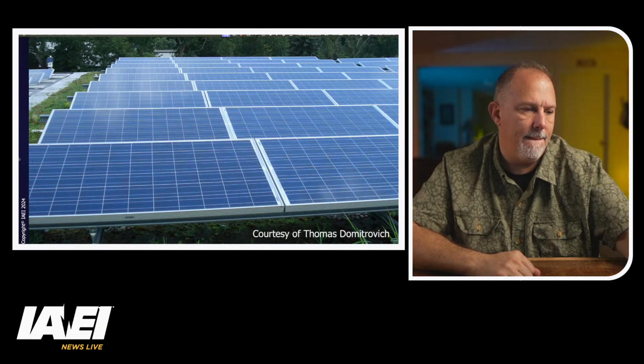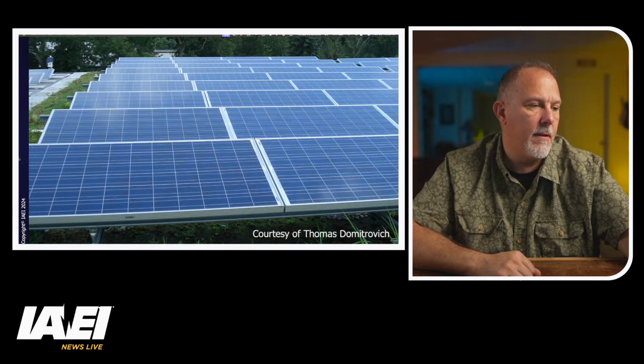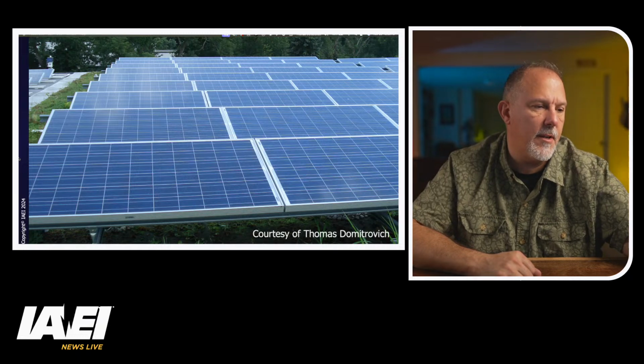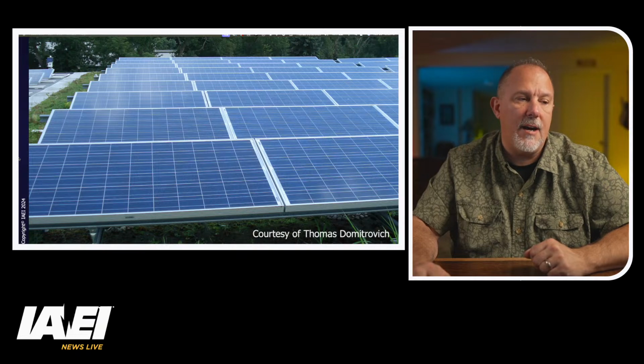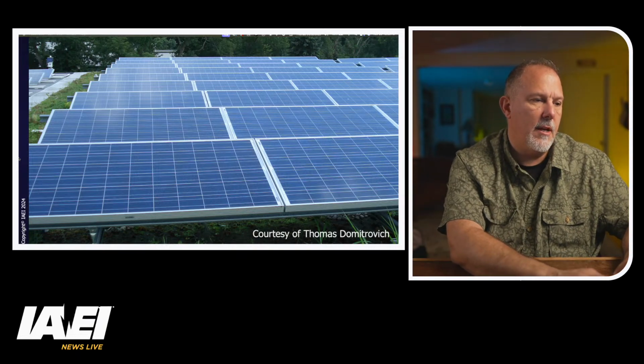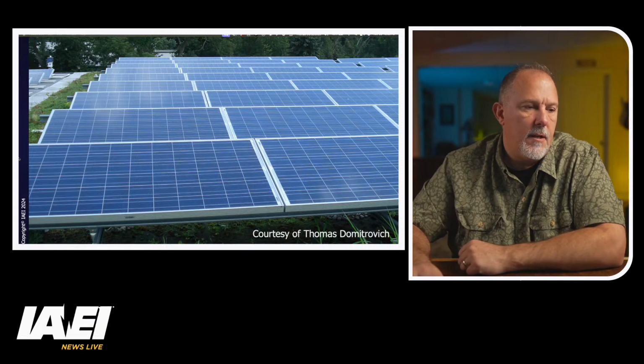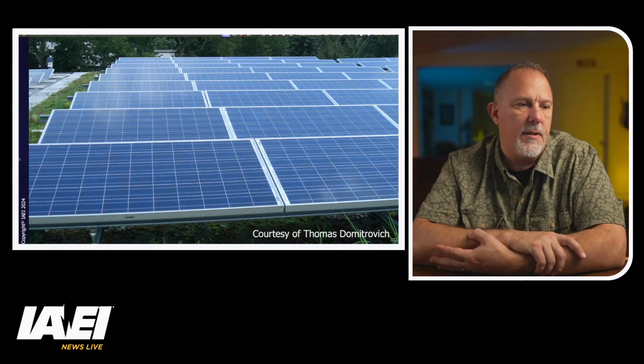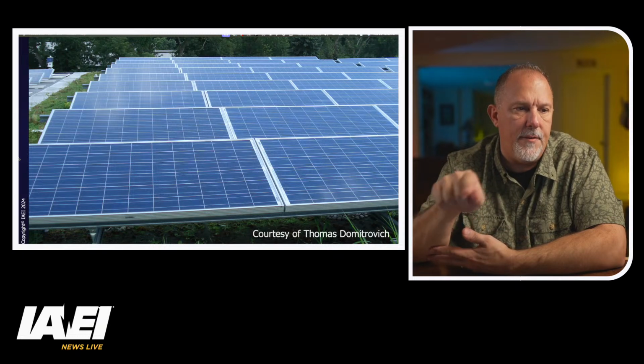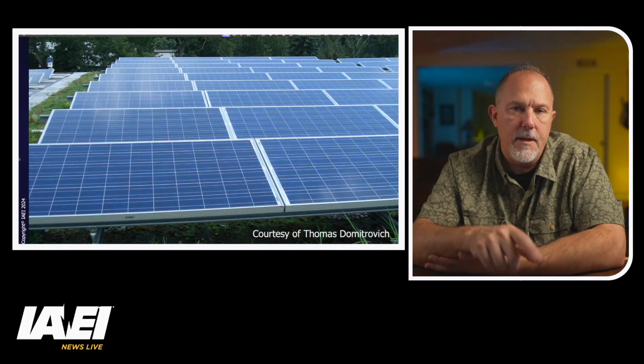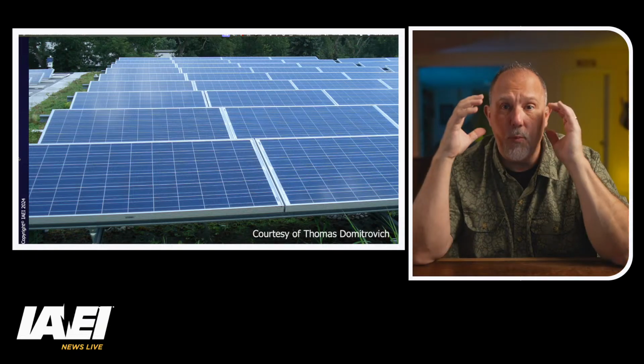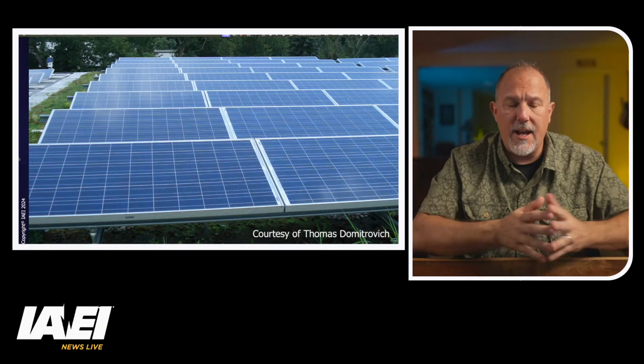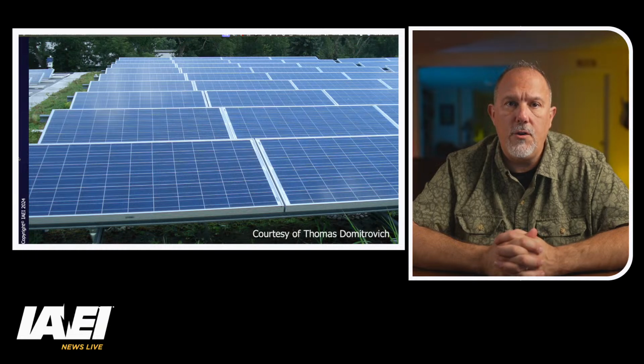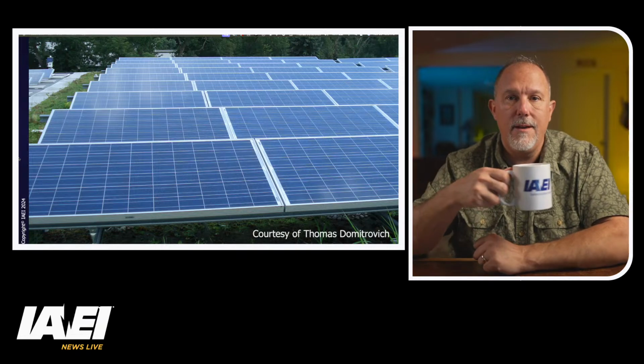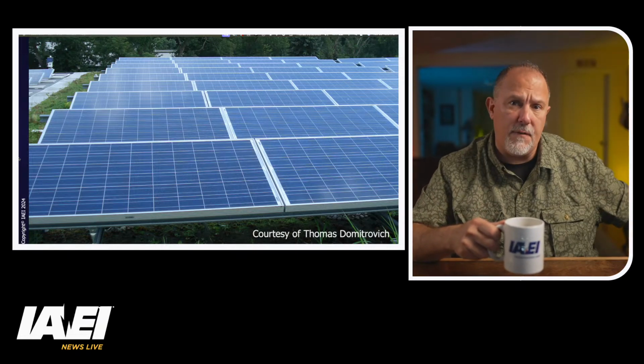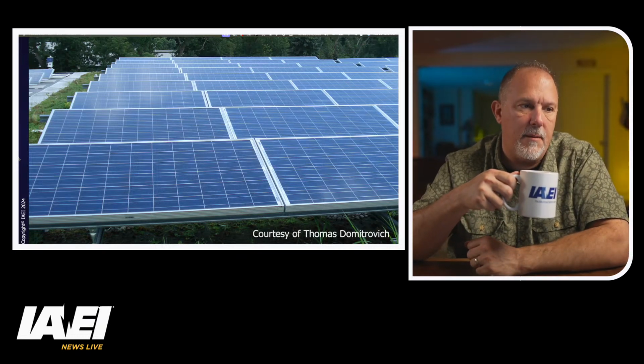In 705, in fact, in Article 100, I believe in the 2023 code, they defined a power source output conductor. Let's take a look at that. Power source output. So they have a definition of a power source output conductor, and it's defined as the conductors between power production equipment and the service or other premises wiring. So they sort of relabeled what we know as the definition of a feeder. So you have to be careful when you're looking at PV systems. It looks like a feeder. It smells like a feeder. It meets the definition of a feeder, but they elected to redefine it as a power source output conductor.